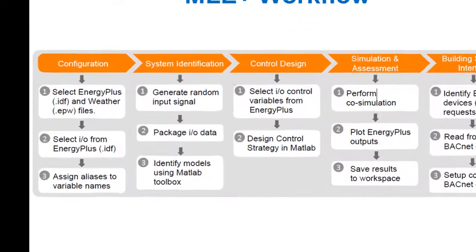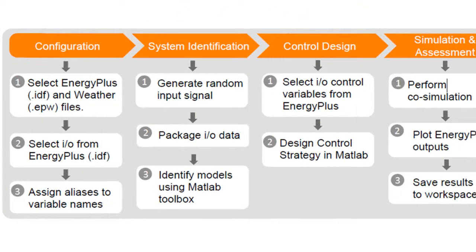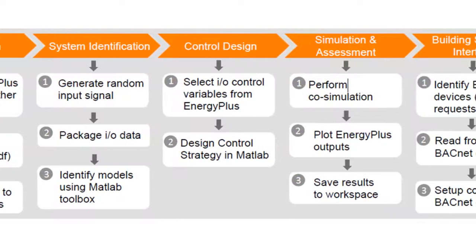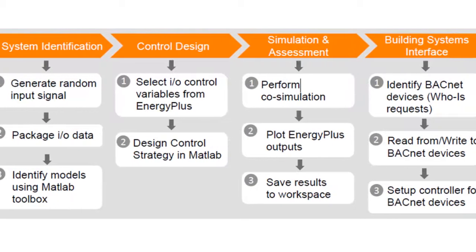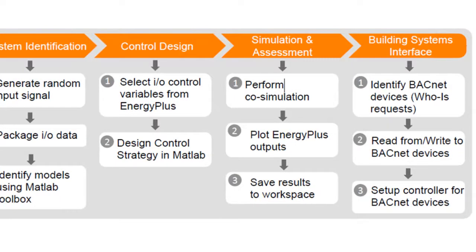The development workflow, as shown in the video, facilitates a complete design cycle. The MLE+ front end uses this workflow to streamline the necessary steps. First, it provides an interface to configure the co-simulation parameters. Second, it allows model estimation of the EnergyPlus building model in the system identification section. This is followed by the control design module, where the energy efficient controller is coded in MATLAB. Then the simulation and assessment module, where you can run the simulation and visualize the results. Finally, the building system interface allows deploying the control algorithm in a real building through the BACnet protocol.